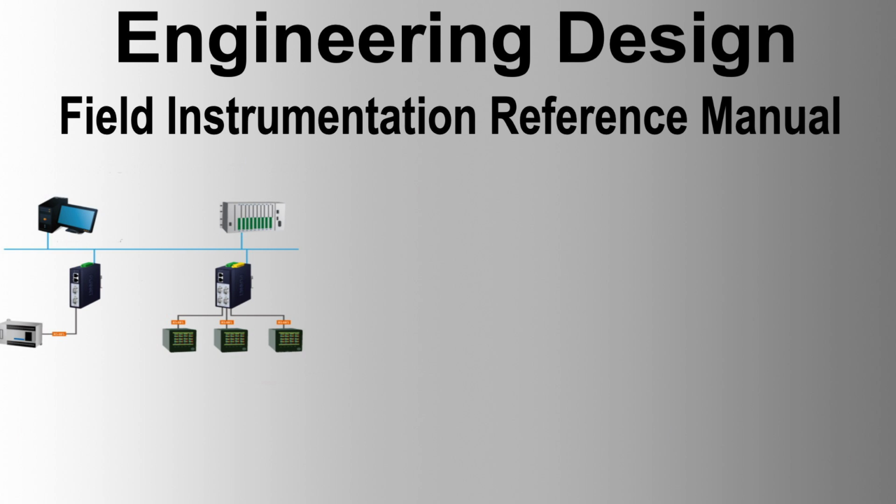Electromagnetic compatibility, EMC. Instruments should comply with the latest EMC policies, and metal cable glands should be used for instrument signal cables with proper earthing connections.